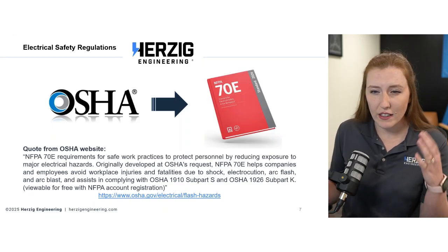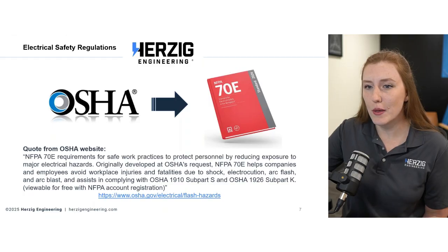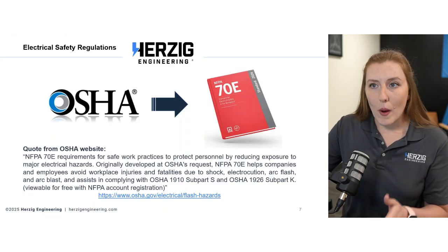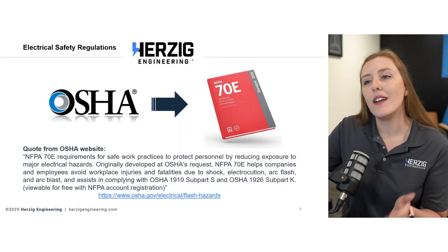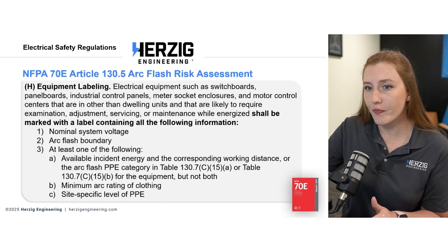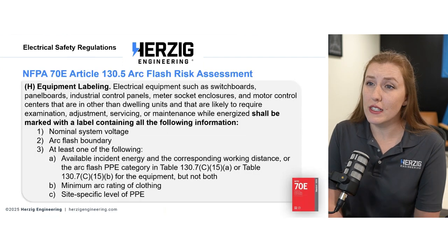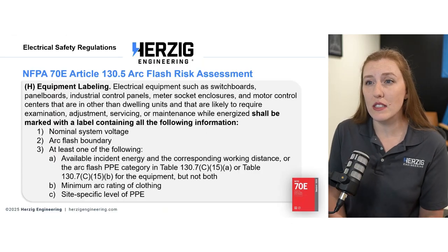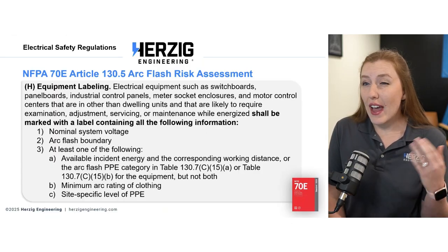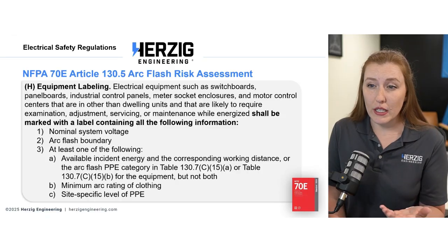Okay, I'm paraphrasing here. The quote's right there on the screen. Again, you can go to the website. But it is required to address arc flash hazards. The 70E tells you how. So for those arc flash risk assessments, there's a few ways to determine the severity of the hazard, and that can be looked at through the equipment labeling as well.